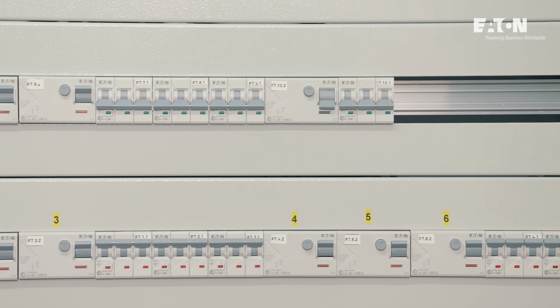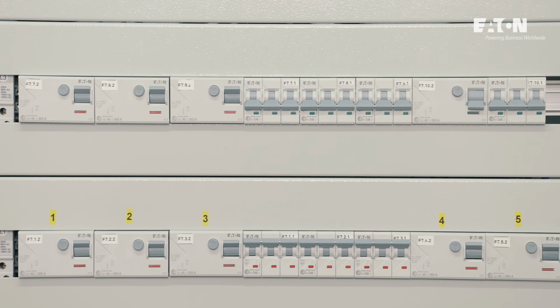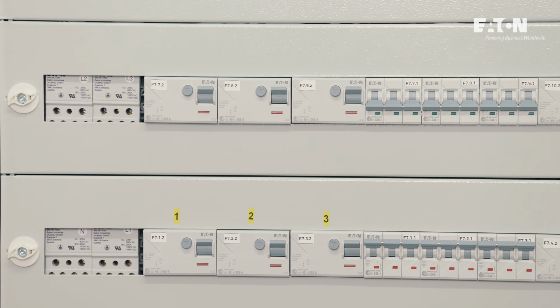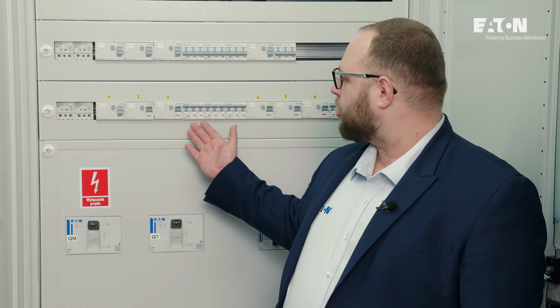Green Motion Building EV chargers are equipped with an integrated DC current sensor capable of detecting ripples exceeding 6 milliamps. Consequently, these devices can be protected using a Type A circuit breaker.